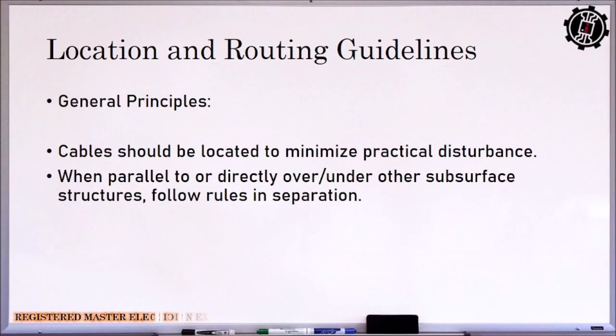So natural hazards and other conditions in cable installation. So natural hazards. So routes through unstable soil, shifting sand dunes, or other natural hazards should be avoided. So hindi pwedeng maglagay ng underground cable, no, in unstable soil. Shifting sand dunes, no, yung mga mabuhangin na mga lupa or other natural hazards. So for example, fault lines, no, hindi pwede doon, no. Hindi pwedeng maglagay ng cable, no, underground cable. If burial areas with natural hazards is necessary, cable should be constructed and installed to withstand potential damage. So if wala talagang other way but to have your cable go, no, on that fault line or sa unstable soil, so dapat there will be a way, no, to minimize, no, the effect of those unstable soil. The protective measure should become compatible with the local installations.